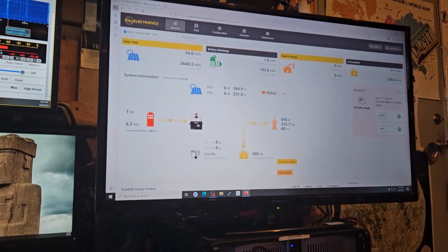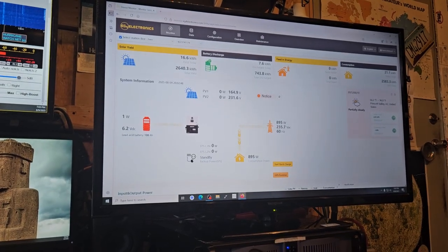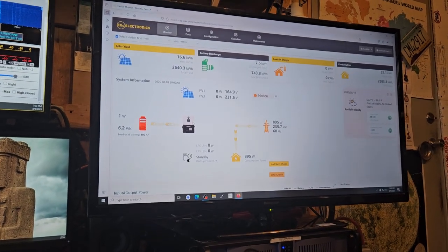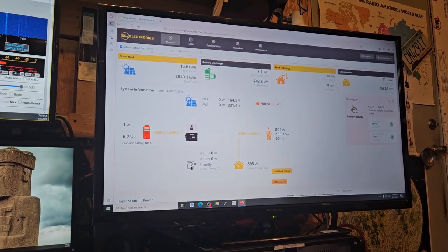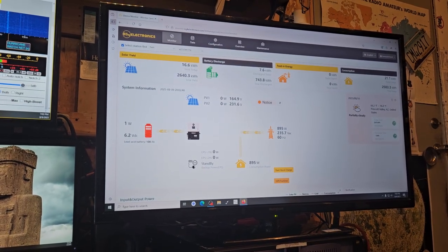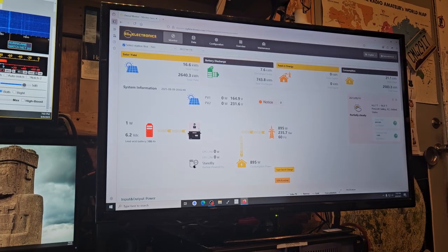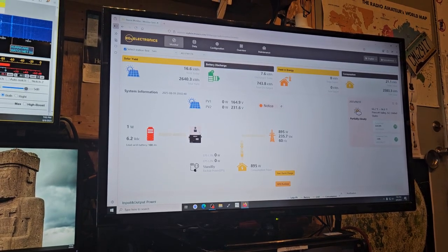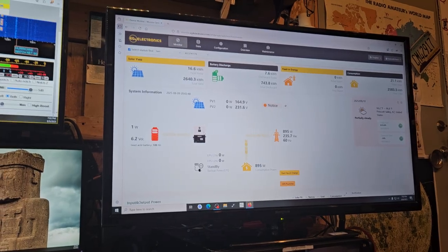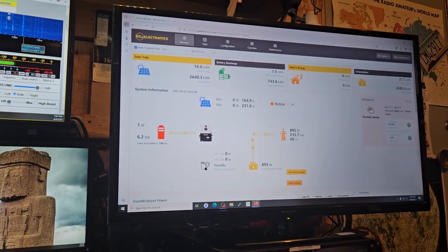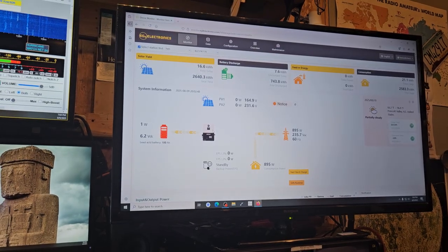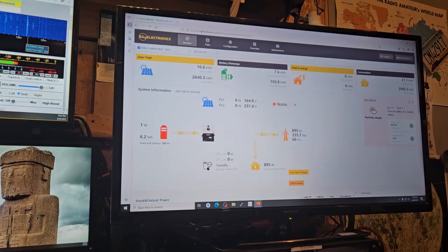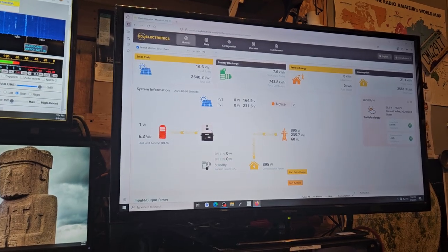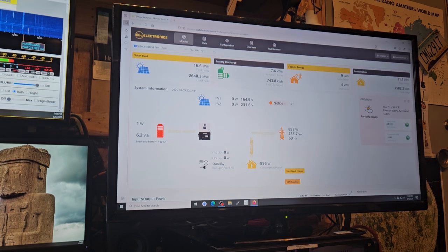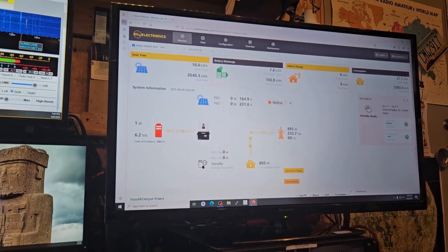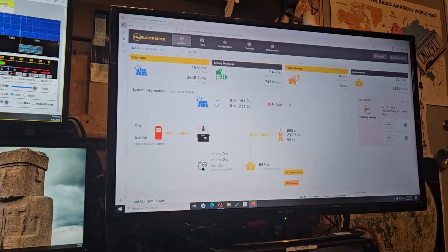But also, since you can't set when the inverter decides to cut off the grid, it has to be whatever it's pre-configured to, which I think is 10%. If you set your cutoff voltage at 47, you're going to be at like 51.7 volts before it cuts out and goes back to the battery and starts to allow solar to charge.